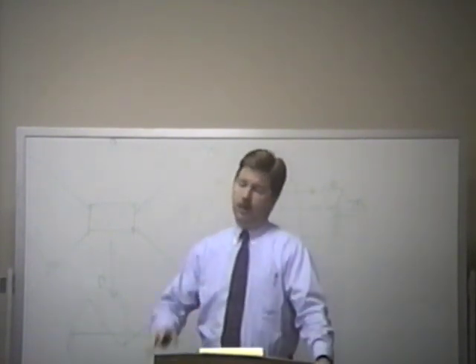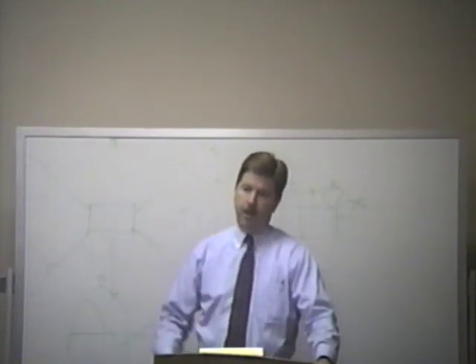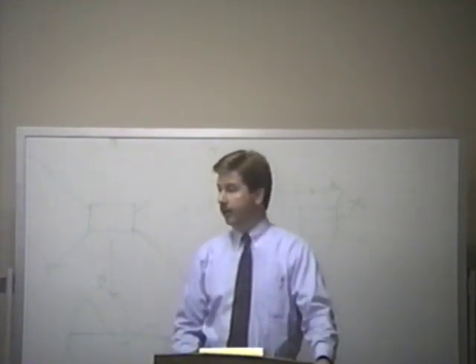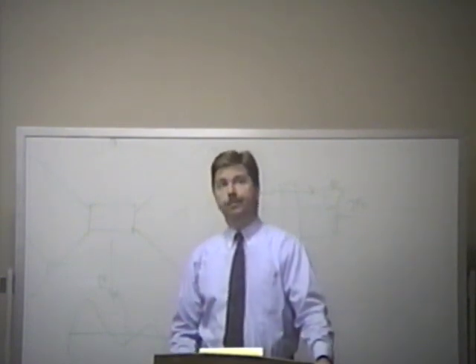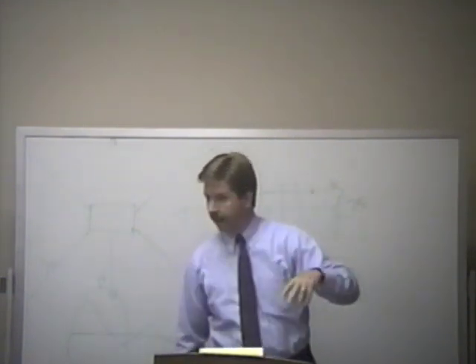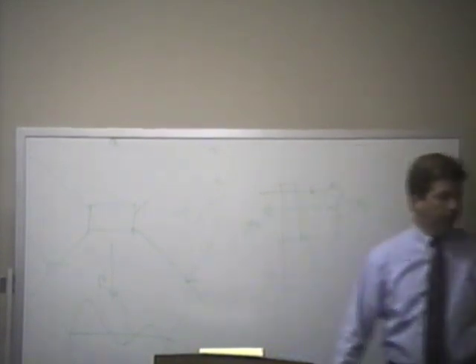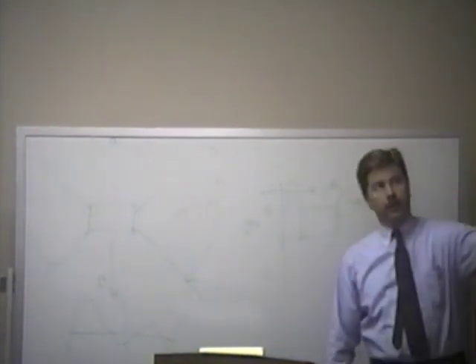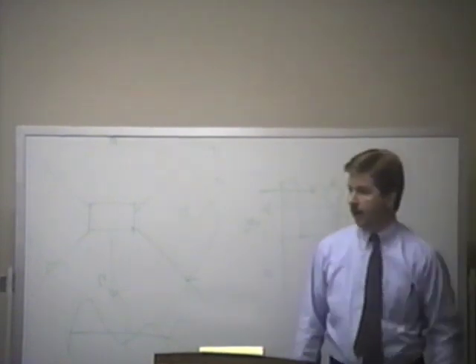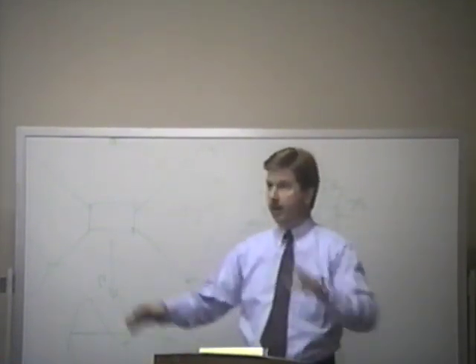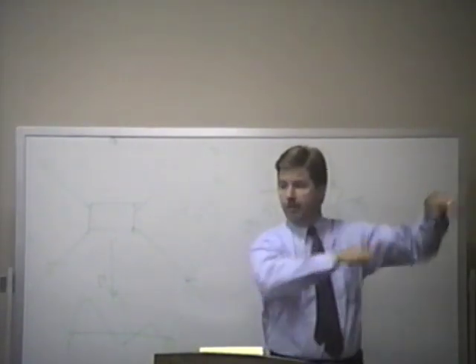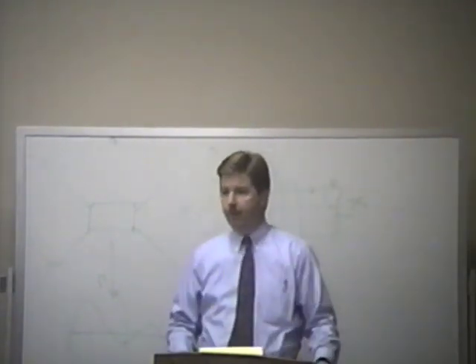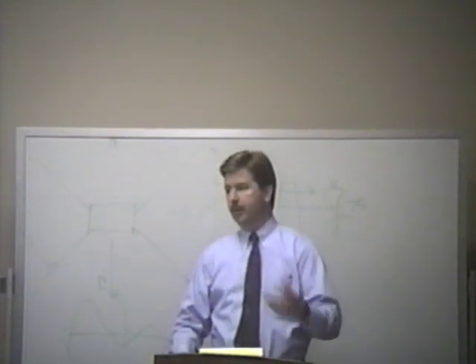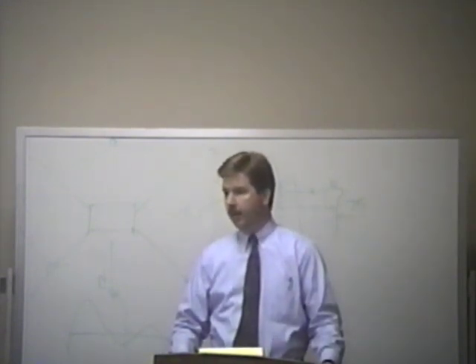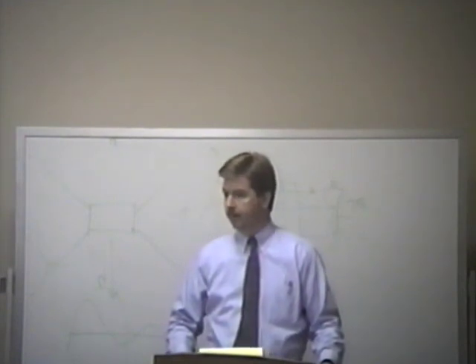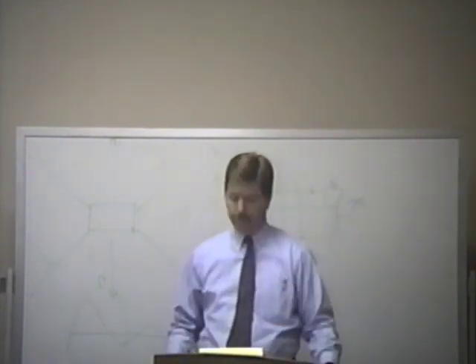Well, with all this cost to run the sheet metal for supply, what they'll typically do is they'll use a plenum for return. They'll just stick a grill in the ceiling in several rooms, and then have a grill way back at the wall on the other side of this room, for example, if this was the air handler room where the equipment was at, we just have a big grill right here. And let the air from this room return directly instead of having ductwork in the ceiling, pick it up, take it through the plenum and back. Well, that plenum, if they use it for plenum return, has different requirements of what you have to do. But that's typically what's done now, because of the economics; they call them return air plenums. Well, that plenum is just that cavity of space, is what that is.